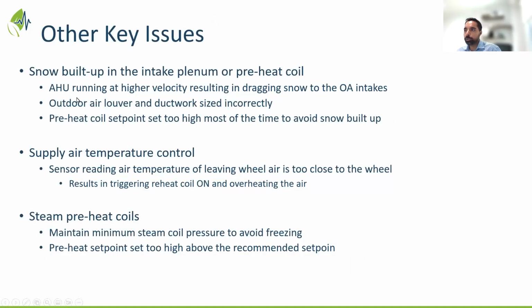Okay, so other issues. This is an interesting one, and I think it's happening at a couple of the HS sites, and it is around the snow build-up in the intake plenum or preheat. As I was explaining, we believe this is primarily because the units are running at a higher velocity across the outside air louver and through all of the components, which is dragging the snow into the outside air intakes, and also all the way towards the first preheat coil.